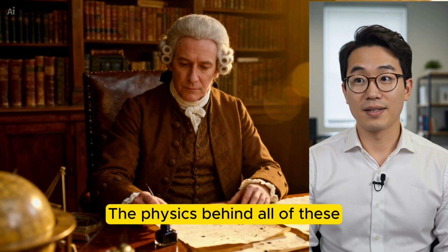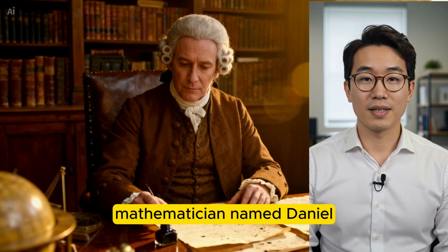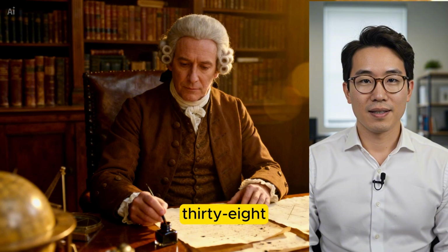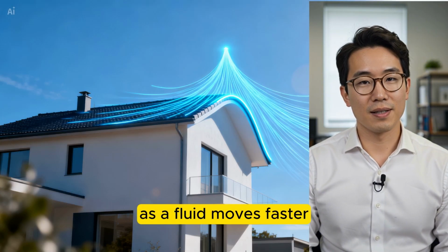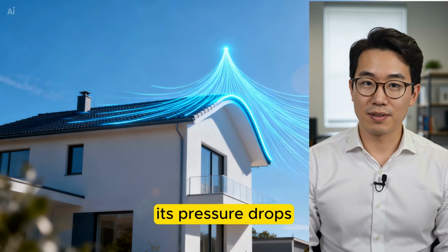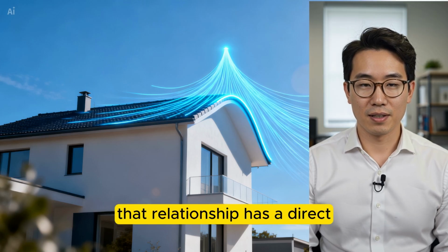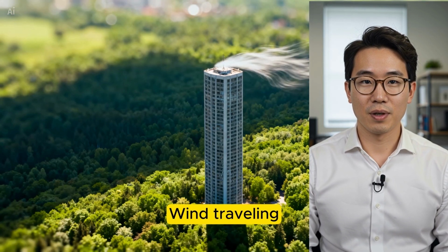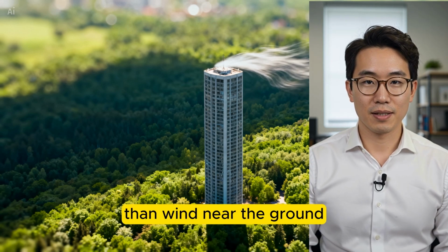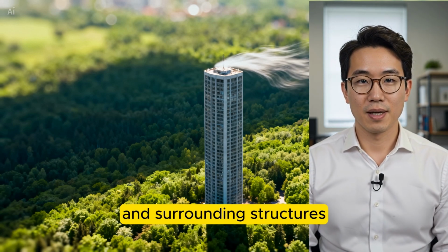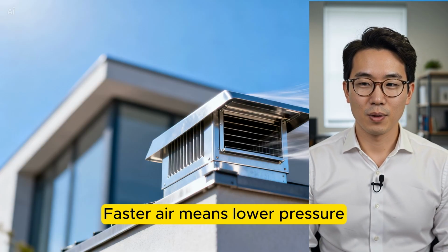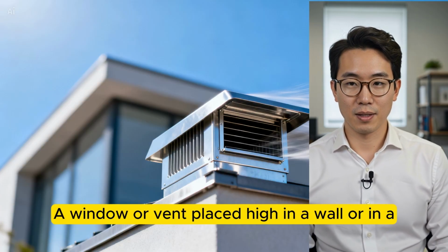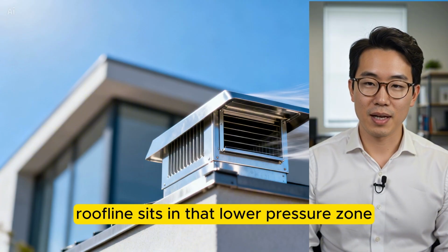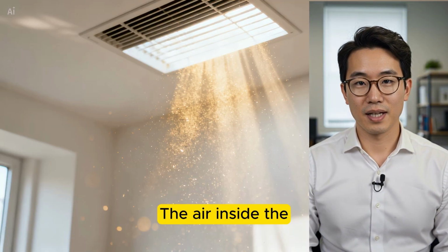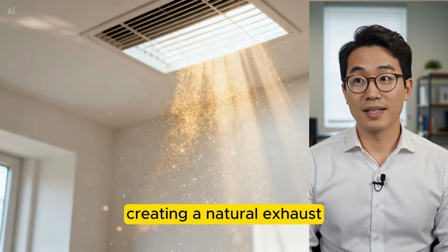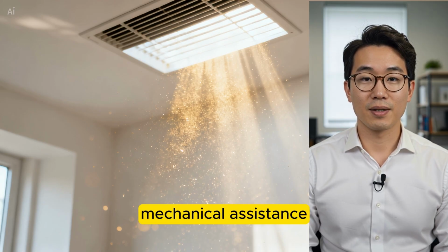The physics behind all of these designs was formalized by a Swiss mathematician named Daniel Bernoulli in 1738. His observation was this: as a fluid moves faster, its pressure drops. And in a building, that relationship has a direct architectural consequence. Wind traveling at altitude moves faster than wind near the ground, which is slowed by trees, terrain, and surrounding structures. Faster air means lower pressure. A window or vent placed high in a wall or in a roof monitor above the main roof line sits in that lower pressure zone. The air inside the building is pulled toward it, creating a natural exhaust path even without any mechanical assistance.